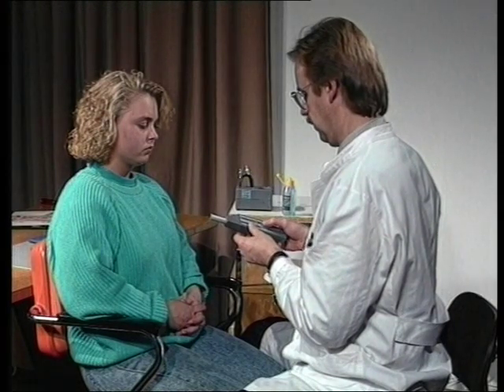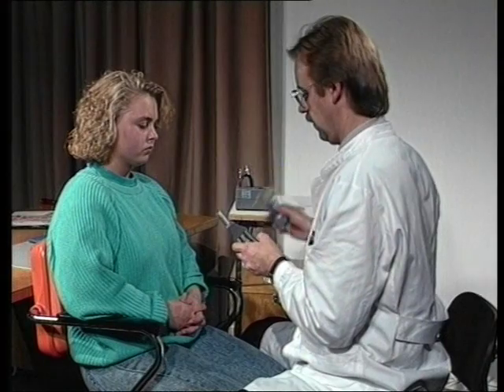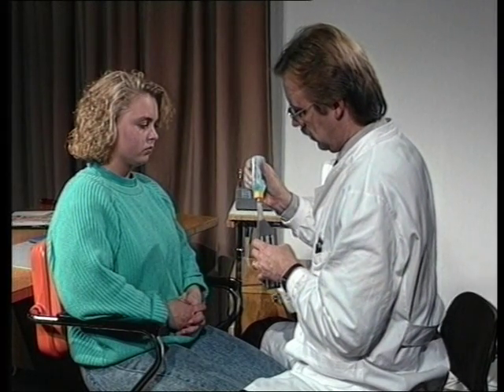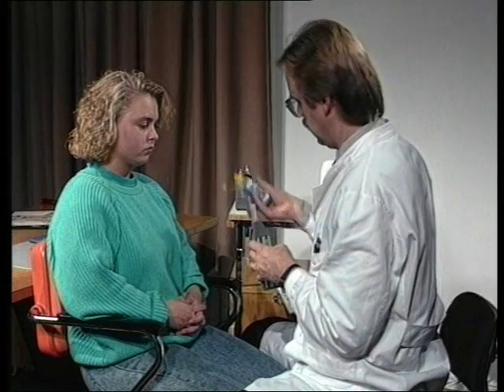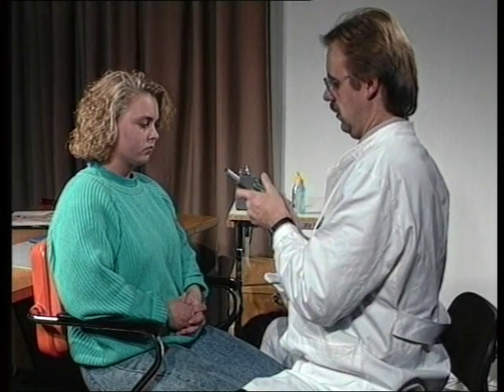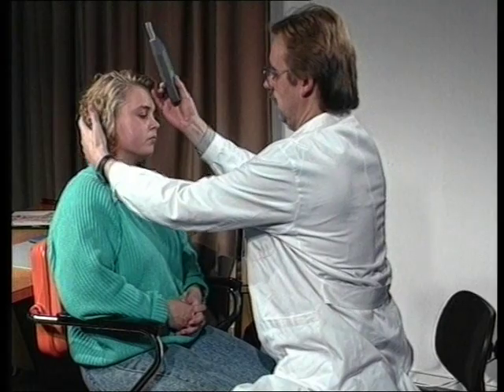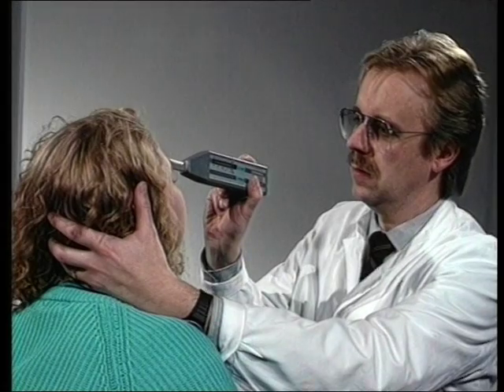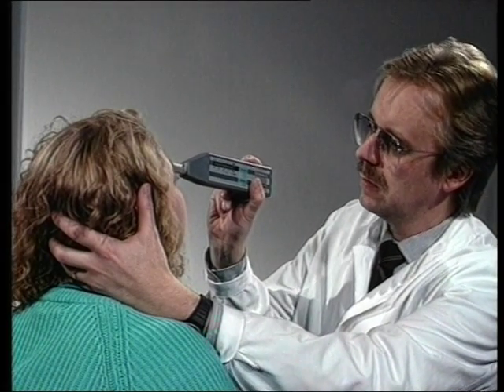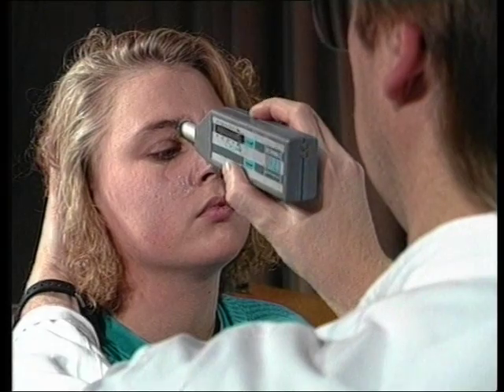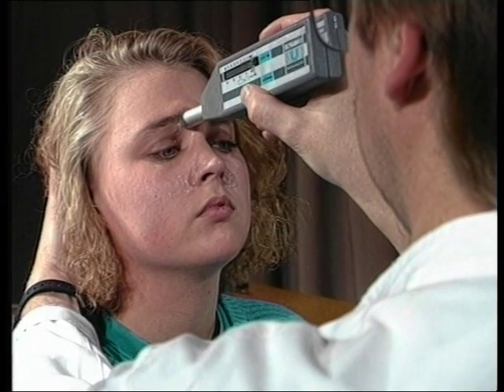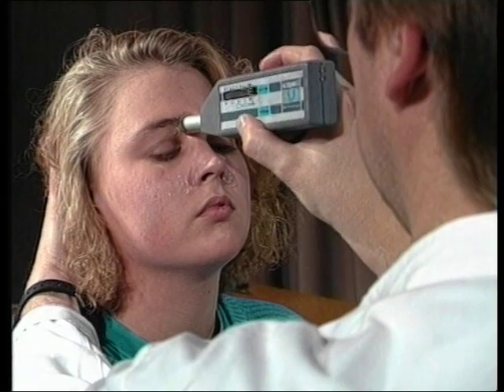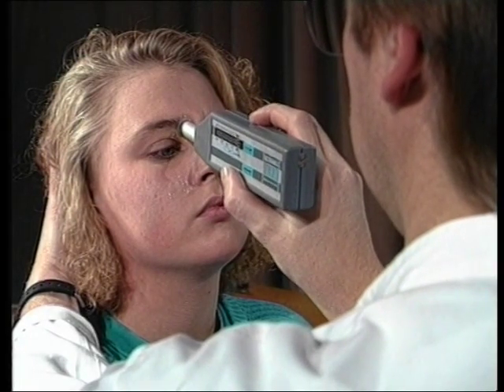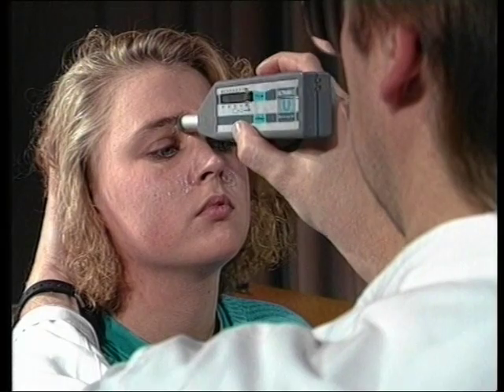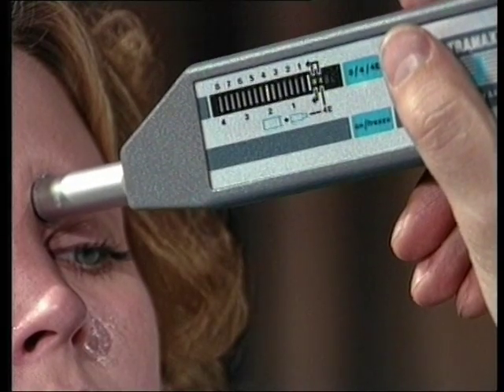When scanning adult frontal sinuses, observe the following points. The 4 cm scale is selected. The contact gel is applied. The patient's head is tilted backwards 30 degrees in order to detect the smaller amounts of secretion. Scanning is started at the floor of the cavity, near the mid-sagittal line, level with the eyebrow. The expected depth of the back wall echo is approximately 2 cm.